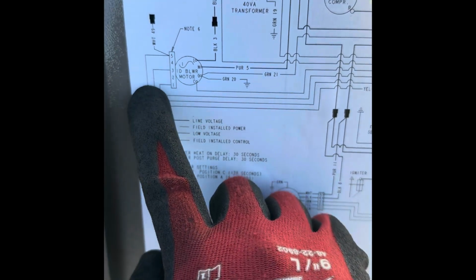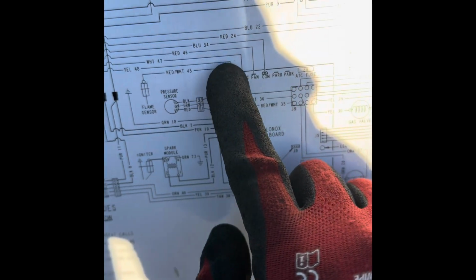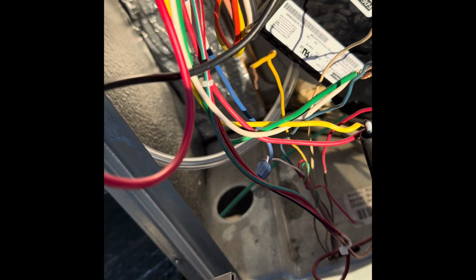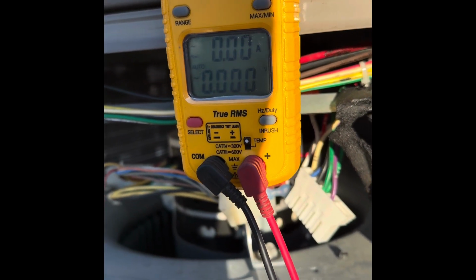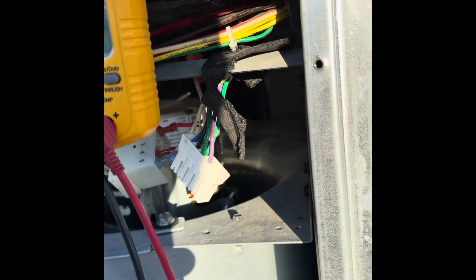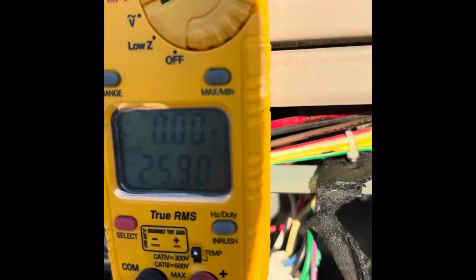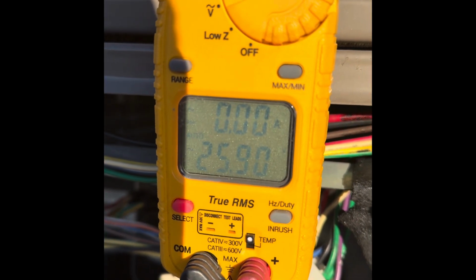And then you also have your cooling, which is going to be one of these speeds, depending on how many CFMs you need, going to the cool terminal. So we should be getting 24 volts there. We're going to jump this out right here. So now we got that. Let's see, maybe one of my clips isn't reading right here. There we go, yep, 24 volts. Okay, so we're good to go right there.